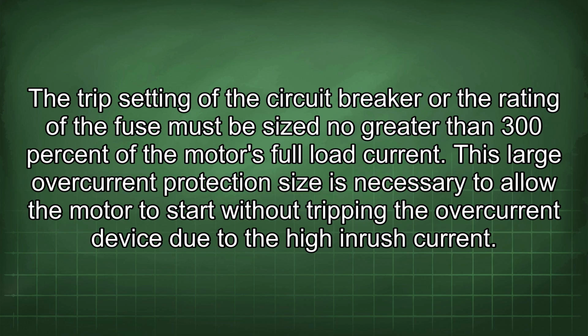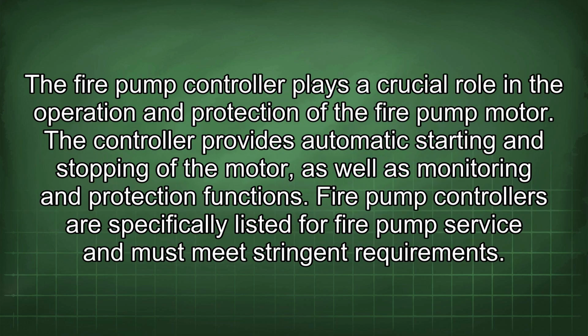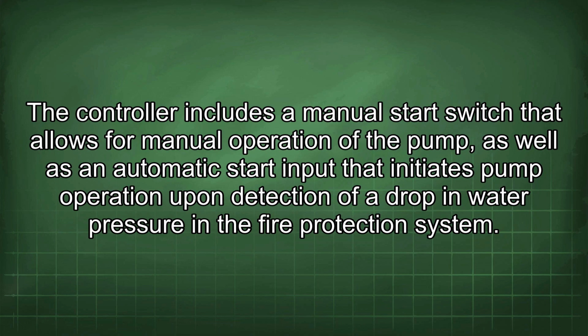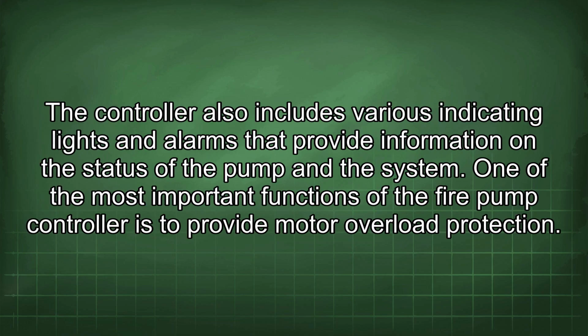Fire pump controller plays a crucial role in the operation and protection of the fire pump motor. The controller provides automatic starting and stopping of the motor, as well as monitoring and protection functions. Fire pump controllers are specifically listed for fire pump service and must meet stringent requirements. The controller includes a manual start switch that allows for manual operation of the pump, as well as an automatic start input that initiates pump operation upon detection of a drop in water pressure in the fire protection system. The controller also includes various indicating lights and alarms that provide information on the status of the pump and the system.